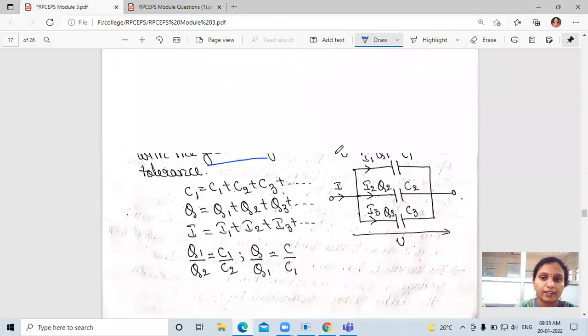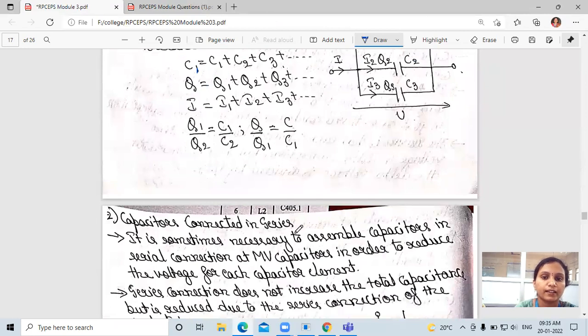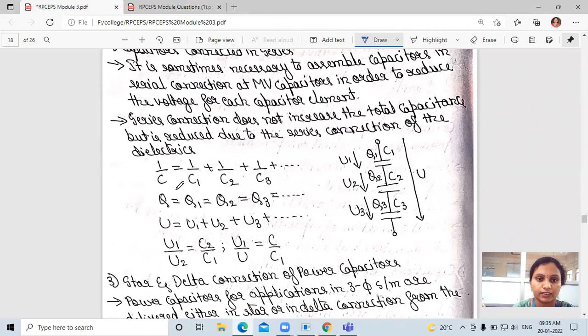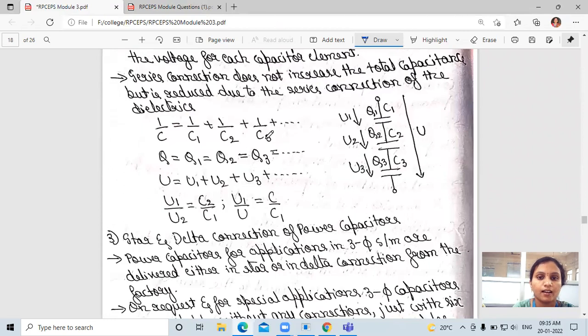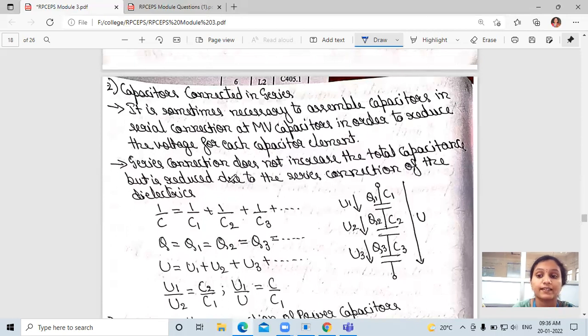Capacitors connected in series: it is sometimes necessary to assemble capacitors in series connection, especially for medium voltage capacitors, in order to reduce the voltage across each capacitor element. Series connection does not increase total capacitance; it is reduced. The formula is 1/C equals 1/C1 plus 1/C2 plus 1/C3. The charge Q equals Q1 equals Q2 equals Q3. The voltage distributes as U equals U1 plus U2 plus U3, and the ratio U1/U equals C/C1.